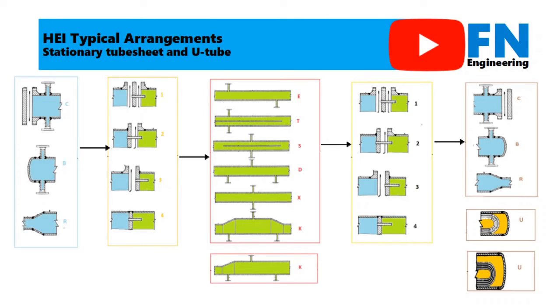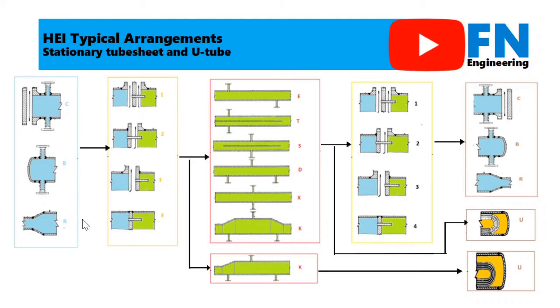Meanwhile, for the shell arrangement using a U-tube, the stationary tubesheet arrangement in the rear head is not required because the U-tube only has one tubesheet. So, the U-tube only consists of four parts: tubesheet closure in the front head, stationary tubesheet in the front head, shell arrangement, and tubesheet closure with type U.